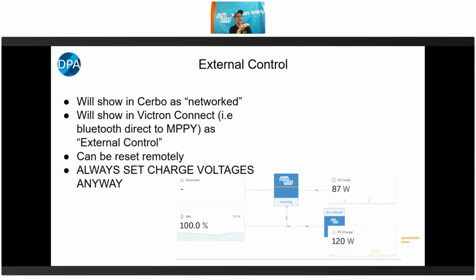The main thing to know about this is that even though the Cerbo and the BMS are taking over responsibility for what the charge voltage of the battery is, you still need to set the MPPT's voltages anyway. That's because it can lose comms to the battery, and it's supposed to then stop charging when that happens. But actually, if the whole system powers down and then boots back up again, it will just start charging according to its settings, and then it could overcharge the battery if you haven't got them set up.